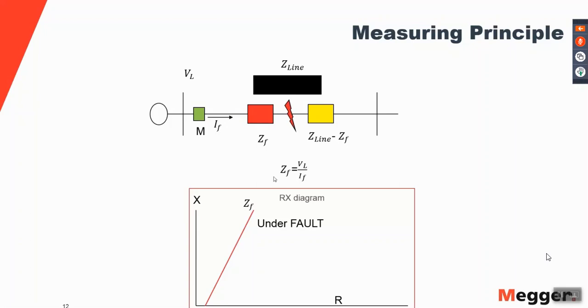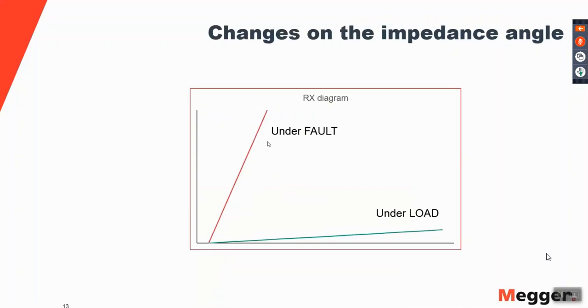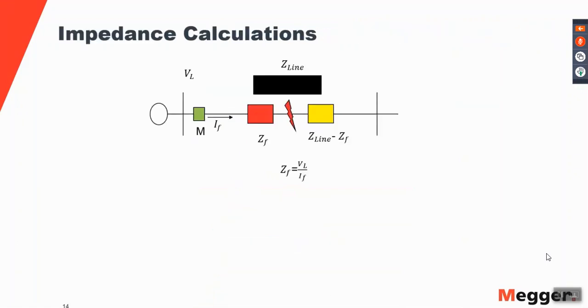Now, if we take this line and we don't consider any three-phase system, the impedance would be simply the voltage measured at this point divided by the current that's circulating through the fault and back to the source. And then we can say that the impedance to the fault is simply this voltage divided by this current. Now, we know that that is not that simple. Why?